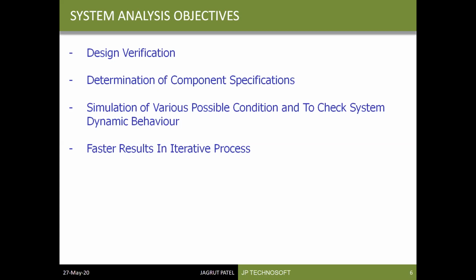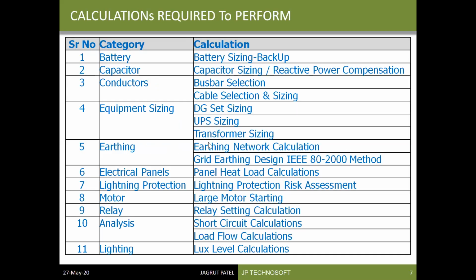Now, to do all these things in a practical way is sometimes not possible. So it is better to have performance analysis on simulation tools. By performing simulation, we can achieve faster results in iterative process like load flow analysis. For a new project, these are the calculations which are required to perform for any kind of electrical distribution network project. This covers battery sizing. To have reactive power management, we should have capacitor sizing calculation, and we should know where to locate these capacitors. That means reactive power compensation mode is important to know. Then for conductors like cables and bus bars, we should have separate calculations to size the bus bar and cable.